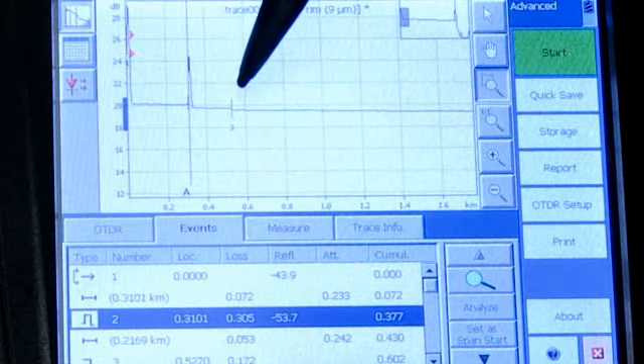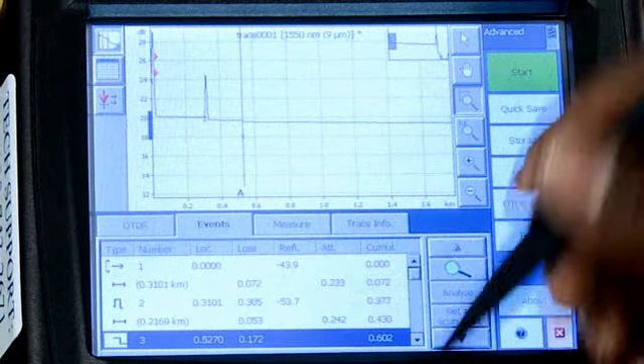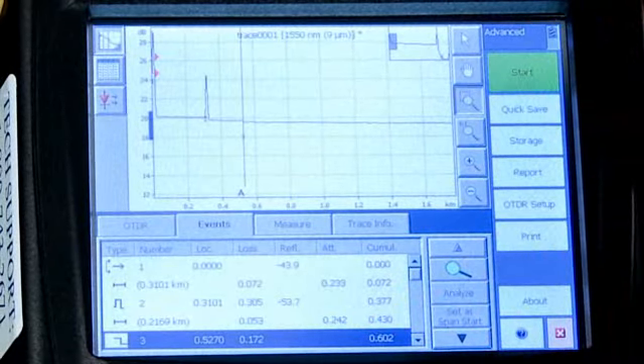The third event is a splice connecting the two reels, and that value is 0.172 of a dB. Again, not too bad. We prefer them to be about a 0.1.